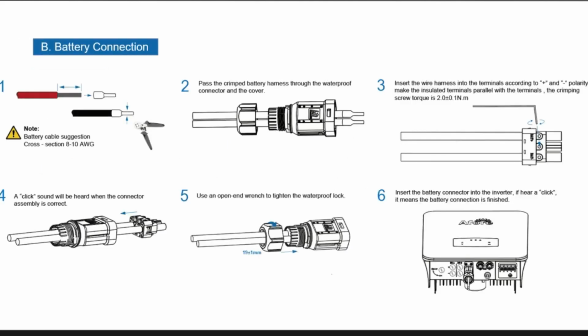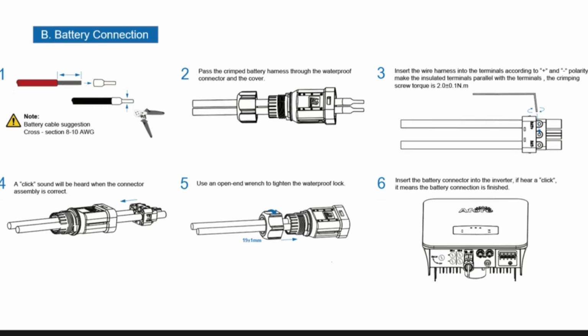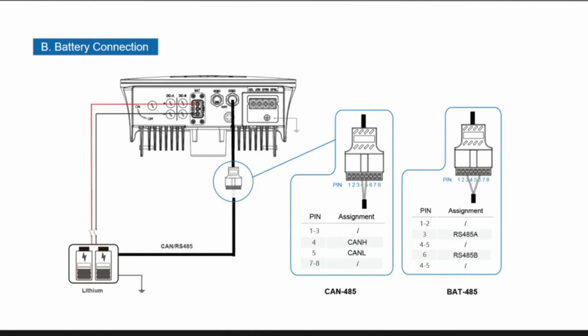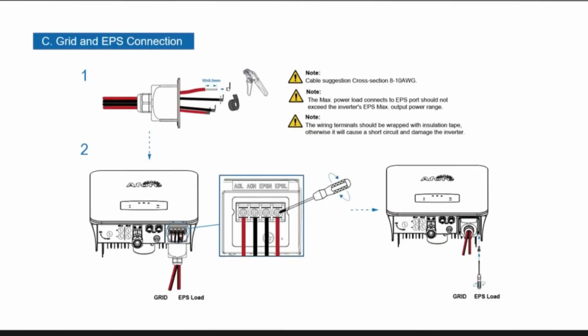I'm sorry, but if you can't screw a bracket on the wall, you shouldn't really be in this, as far as I'm concerned, so we're not going to go through that. This shows you how to connect the battery connections and what the fittings are that come with it. As I say, this is for an AC coupled system. There are two different forms of battery connection on here. There's the RS485, which goes in pin 3 and pin 6. The more common one, for most batteries, is CAN H and CAN L, which goes into the green plug we use, COM2. The battery connection goes into this green plug, which comes in the box, and it also uses the same green plug for the connections.